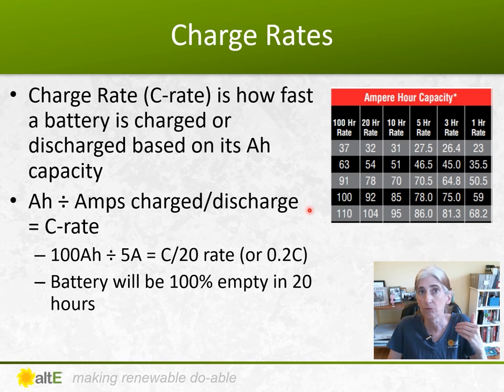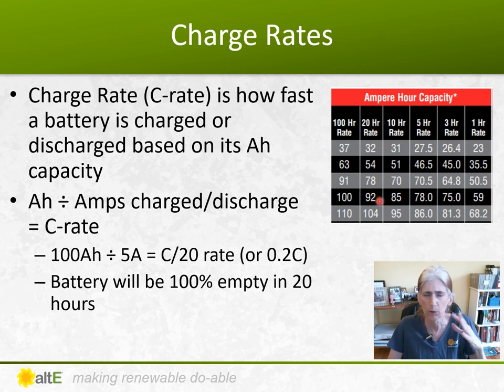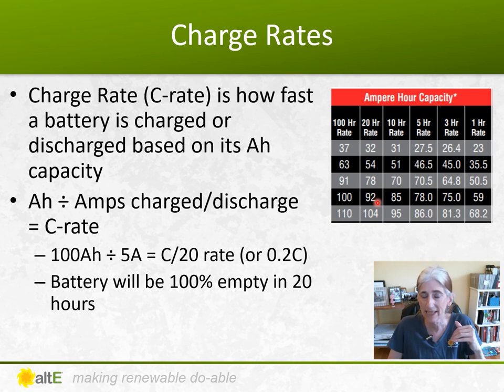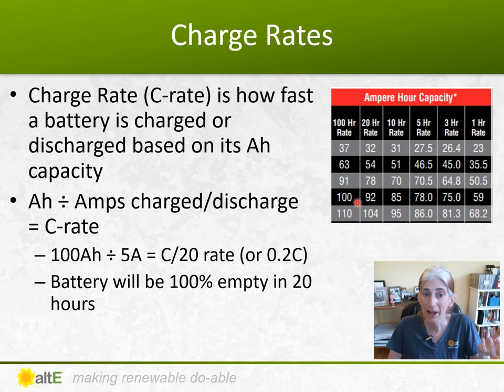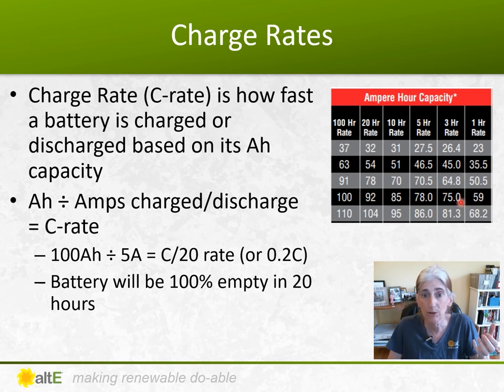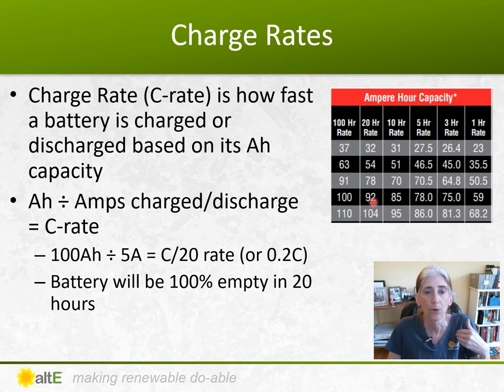Most batteries are rated at the 20-hour rate. At a 20-hour rate, you've got 92 amp hour capacity. But if you pull power out or put it in slower than that rating, you'll actually have higher capacity — up to 100 amp hours if you're gentler with the battery. Drop down to three hours and you're only going to have 75 amp hours available. So based on the charge rate, your capacity changes.